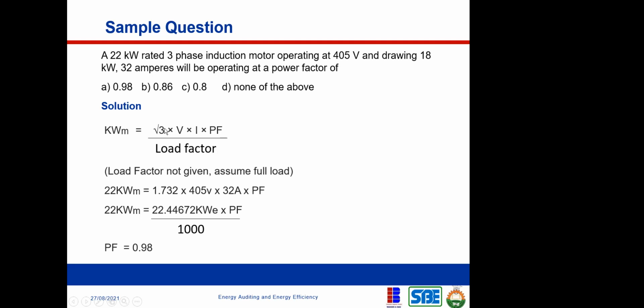So it's the same formula that we have: root 3 times the voltage times amperes times the power factor divided by the load factor. We are looking for power factor, so we can calculate it directly from this formula. We know every other thing, but we don't know what the power factor is. So it's a straightforward question. Here we can calculate what the power factor is.